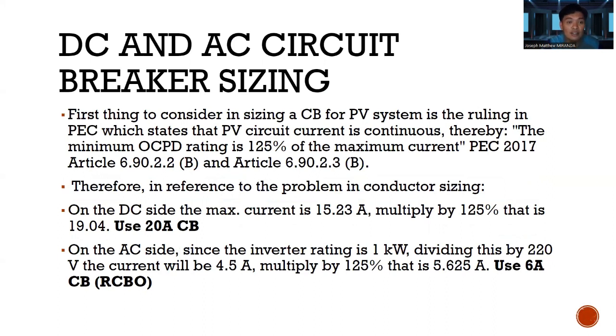So, this is the AC circuit breaker sizing. First thing to consider in sizing a PV system is a ruling in PEC which states that PV circuit currents are continuous, thereby the minimum OCPD rating is 125% of the maximum current, PEC 2017 Article 6.1. So yan yung mga article na pinagkuhanan nitong ating statement. So therefore, in reference to the problem in conductor sizing on the DC side, the max current is 15.23 ampere multiplied by 125%. That is 19.04. Use 20 ampere CB.